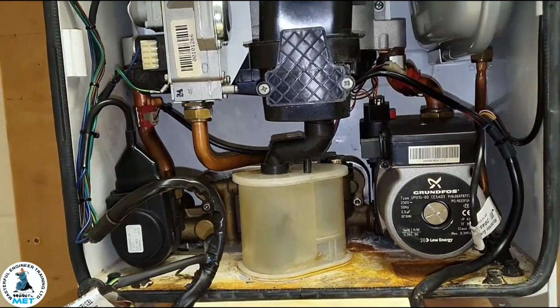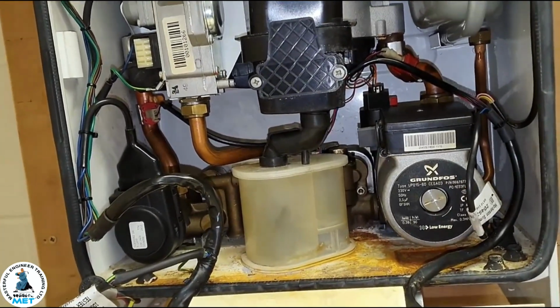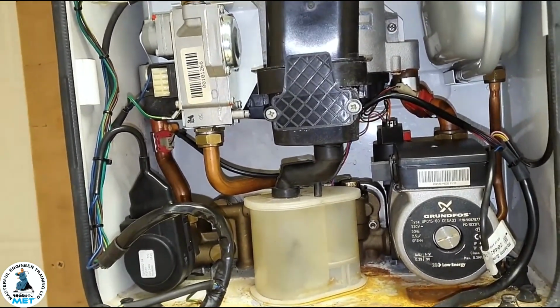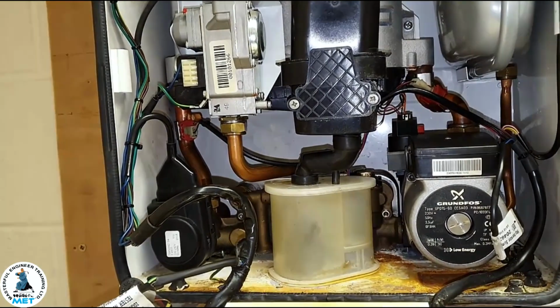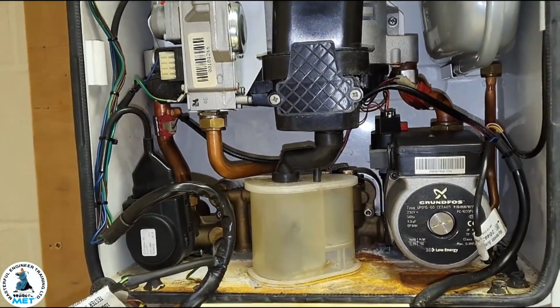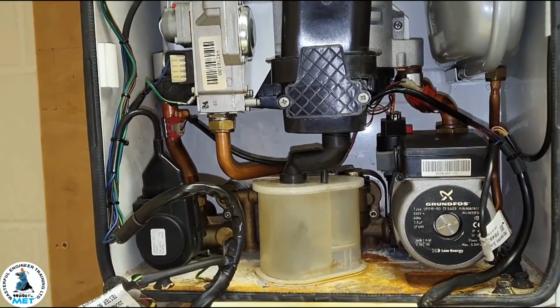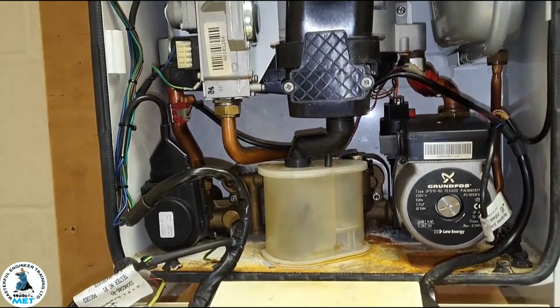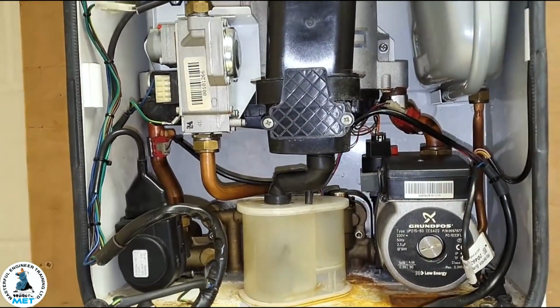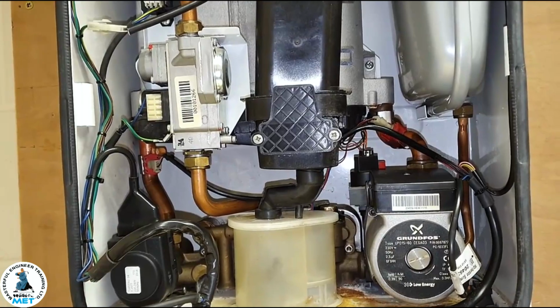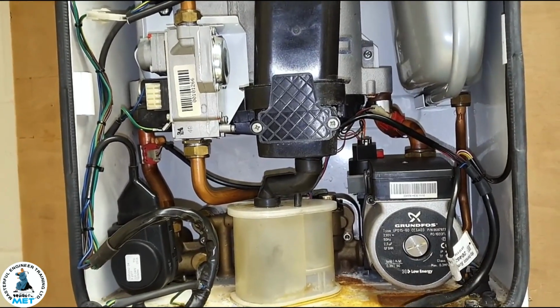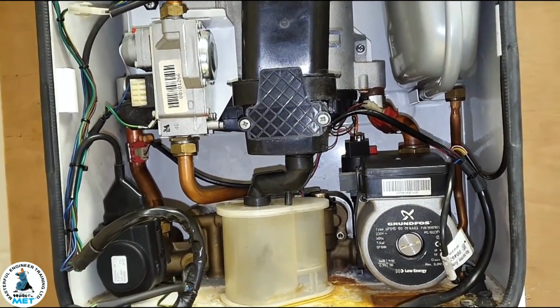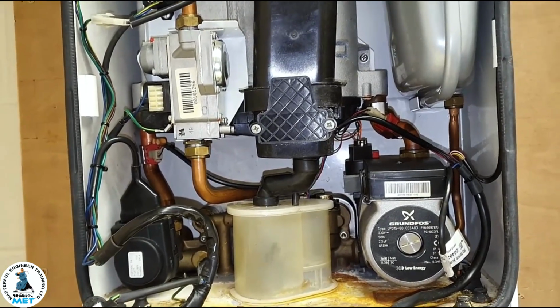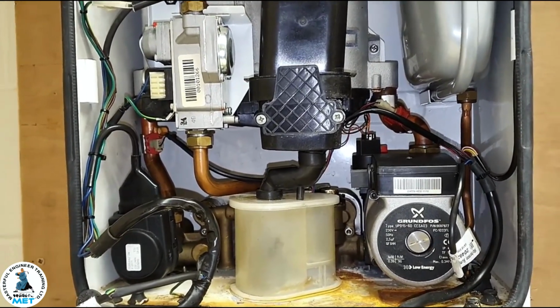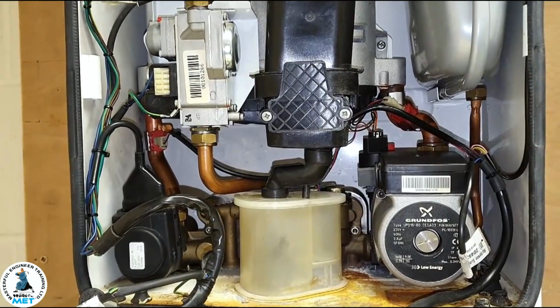So if that was me, I'd say, right, they're telling me the pressure's gone right up. I'm going to ask, when does it happen, is it constant all the time? They say yeah. Then I'd ask, is it when your heating's on, or off? So if they say, well, I've not had the heating on for a few weeks because it's warm, but all of a sudden the pressure went up, not been using it, just gone up.